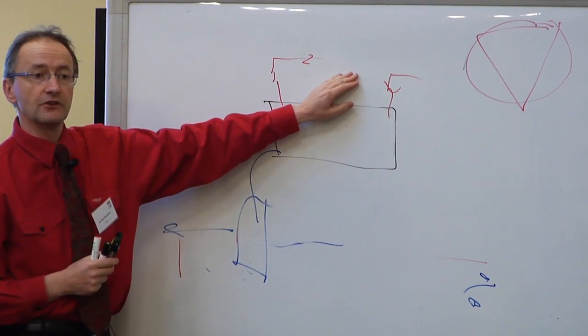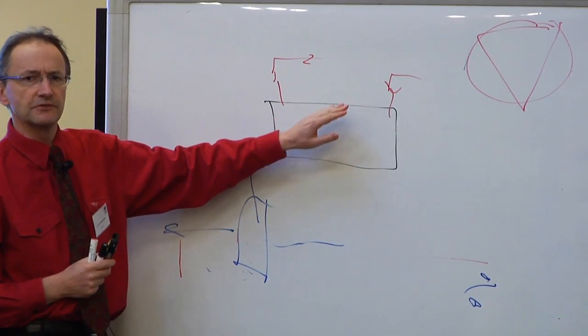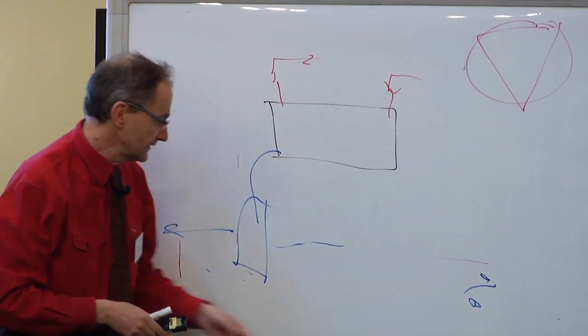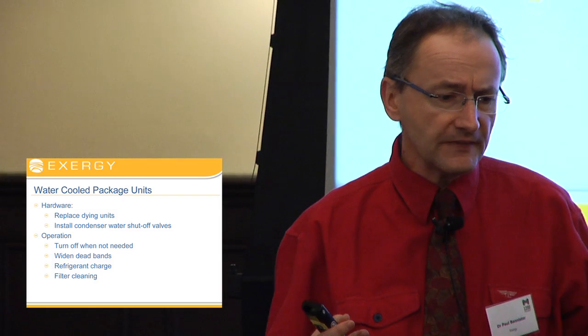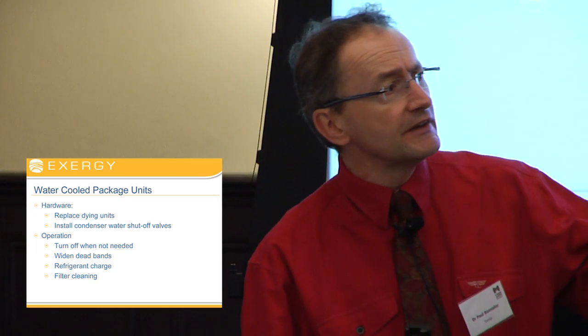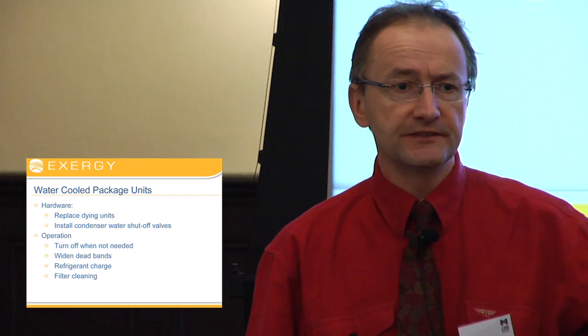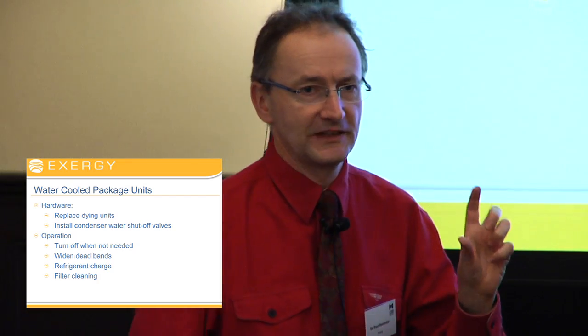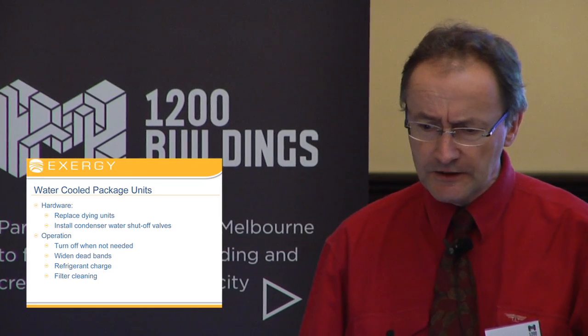So by installing a valve that turns on and off with the package unit compressor, we can make a massive improvement in the energy efficiency of this unit. Again, a case example was a building where we had a condenser water circuit, which had lots of these water-cooled package units on it, and it was running at 80 kilowatts flat load. So the motor that was driving that pump was 80 kilowatts all the time. So we put in isolating valves that just turned on and off, so that they only gave the unit water while there was a demand for cooling, and we reduced the pump from 80 kilowatts to 8 kilowatts. So half a star for that building, just by fixing that.